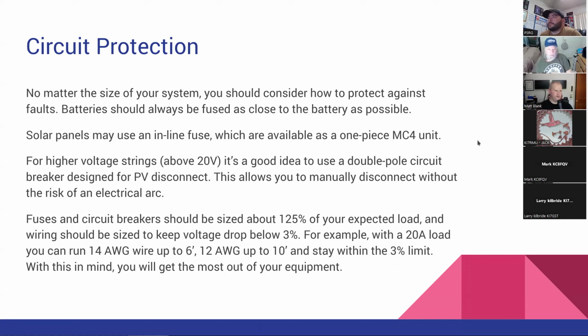For higher voltage strings, use double pole circuit breakers designed for PV disconnect, like I mentioned with arcing before. That's something that makes it safer when it's time to disconnect the system, and safer if there's a fault where one of your high voltage lines is compromised, preventing an arc there. It's not critical if you're just running things in parallel, but I think it's a good idea because it allows you to assemble and disassemble things safely.